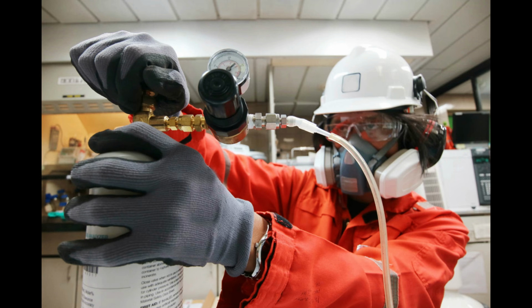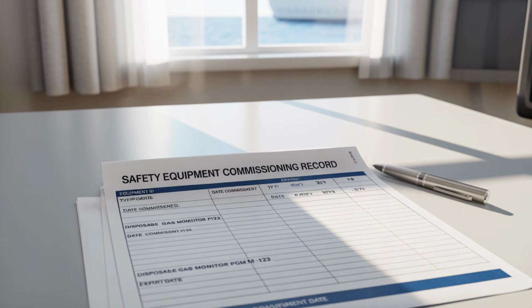Now, let's talk about maintenance. There is a big difference between an operational test and a full calibration. Operational tests, also known as bump tests, must be performed daily or before each use according to manufacturer instructions. Full calibration must follow the company's SMS and the manufacturer's frequency, typically at least once a month. For disposable personal monitors, remember they cannot be recalibrated. They must be discarded once they reach their expiry date. It is vital to record the exact date these disposable units were first commissioned to track their life cycle accurately.